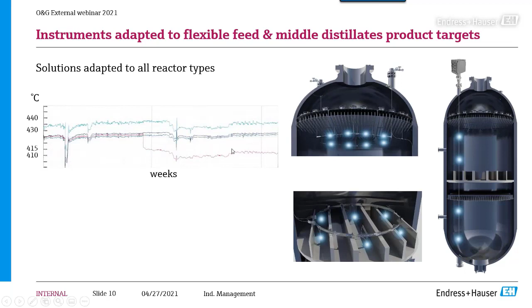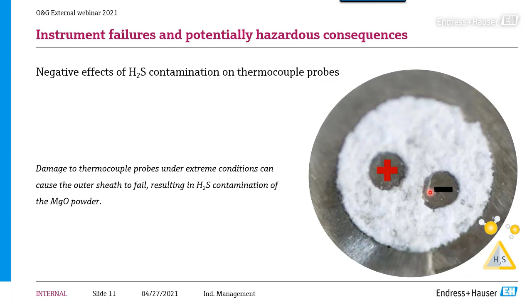And what I want to show you is what can happen. So if we take again a typical thermocouple with the external sheath here, the mineral insulated powder inside here, and two electrodes here, and simulate a crack, we can easily show what is happening. The internal part of the thermocouple, the white area, gets polluted with this blue color, which can be any hydrocarbon fluid.